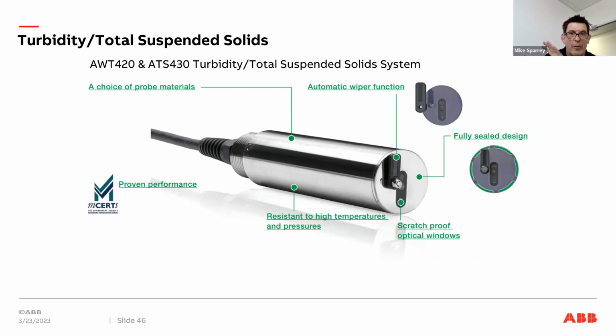As it says there, the sensor itself is fully sealed, so unlike some of our competitors, the only real maintenance, outside of things like verification calibrations, is changing the wiper itself, and that's just a nylon nut that you undo and take off, and put a new one on. So we've reduced the level of maintenance to the bare minimum. The optical is sapphire glass, so it's very resistant to abrasion and bleaching and things like that.